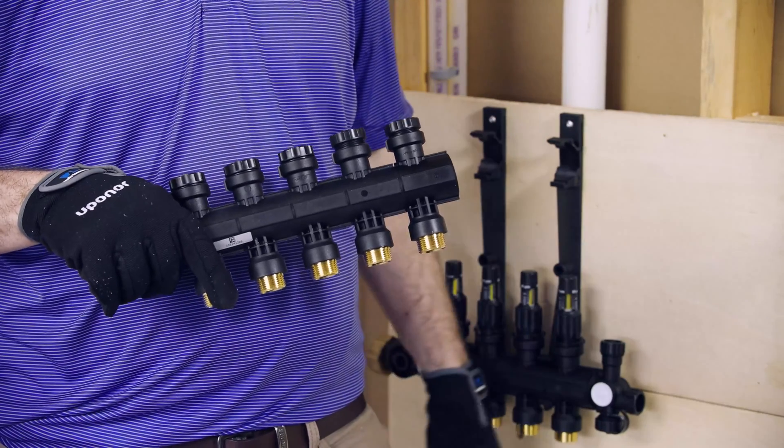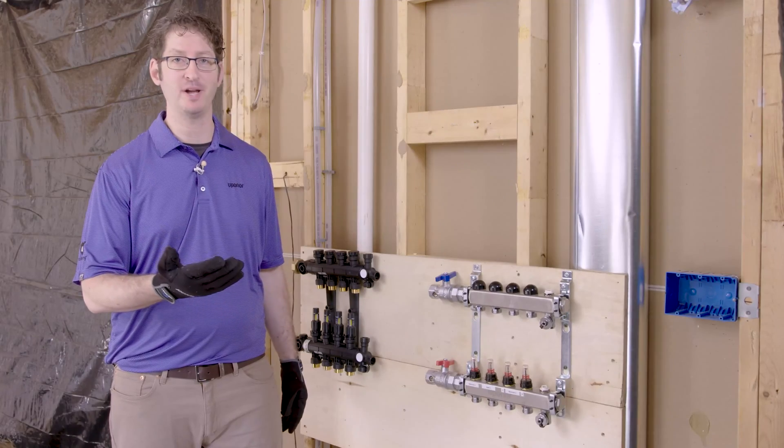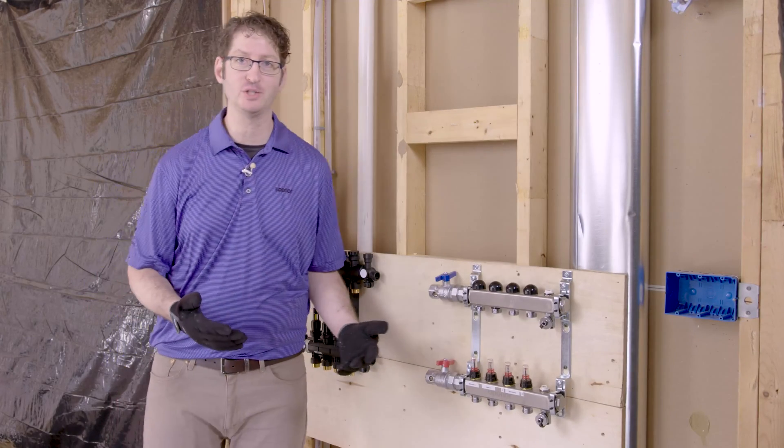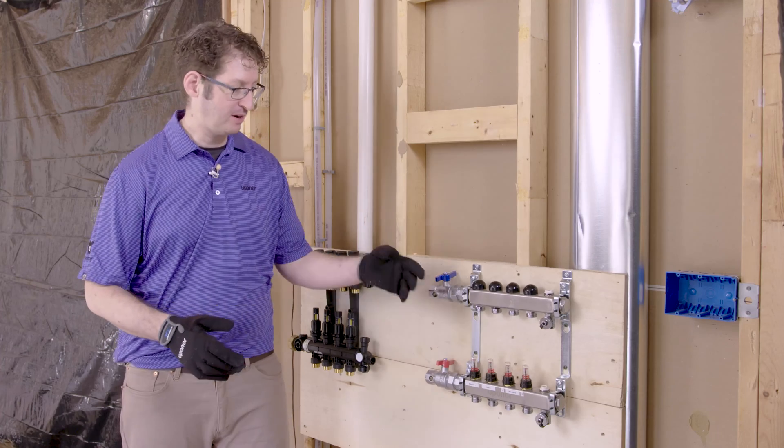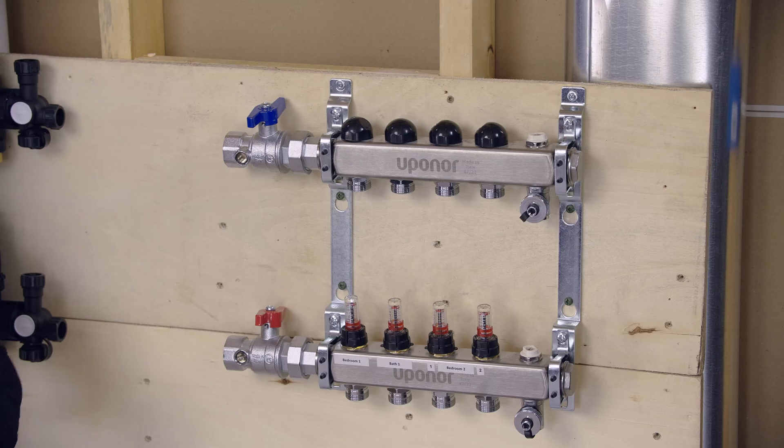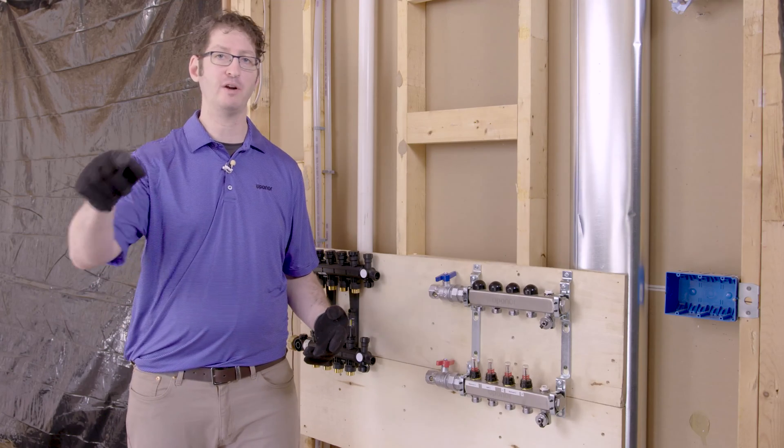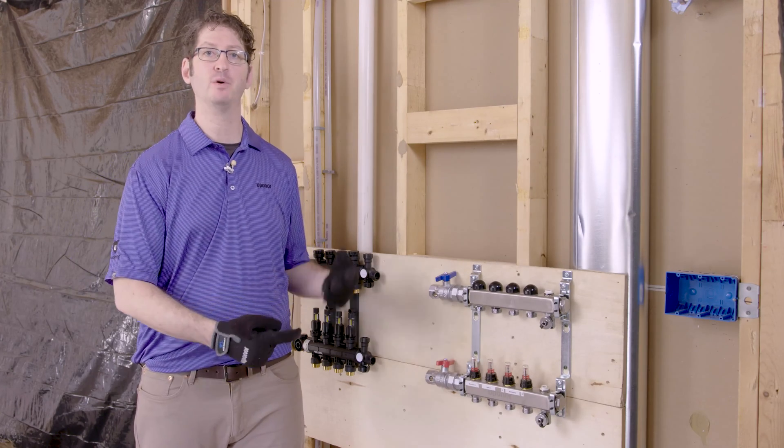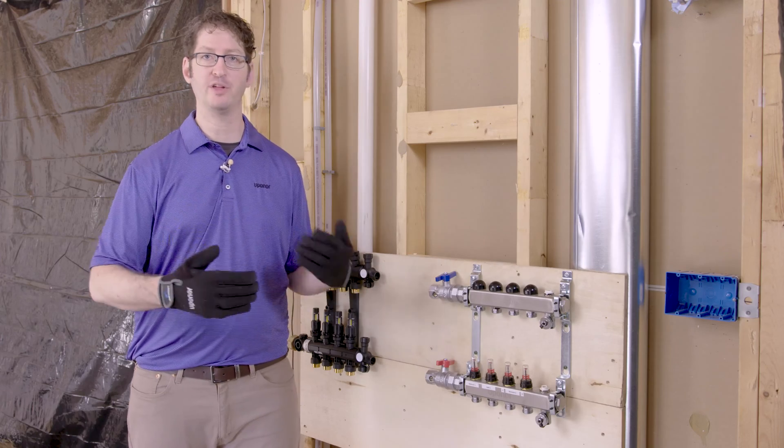Adding water to either one of these manifolds works the same way. This manifold isn't connected to a water supply, but that's not a problem. This manifold has threaded connections on both the supply and return lines where I can hook up a garden hose and run water from a hose bib into this manifold to fill it up and fill all the other loops up.